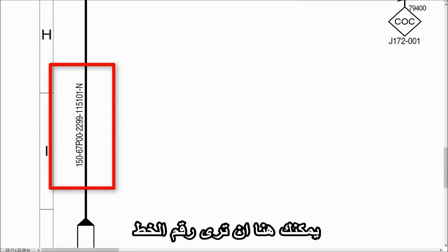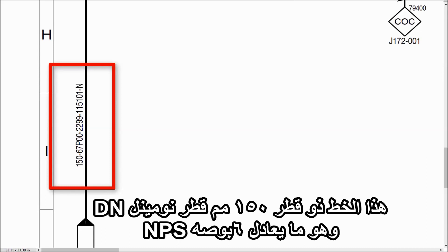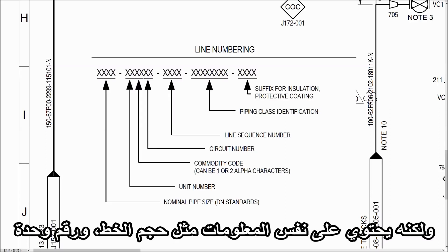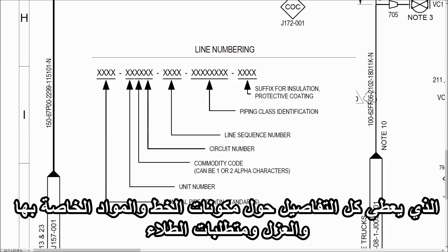Here you can see the line number. It is a 150mm diameter line as per DN standard, which is equivalent to 6 inch NPS. Different companies follow different terminology for the line number, but it contains the same information: line size, unit number, commodity code that identifies the fluid inside the line, circuit number, line sequence number, and piping class — which gives all the details about piping components, their material, insulation, and coating requirements.